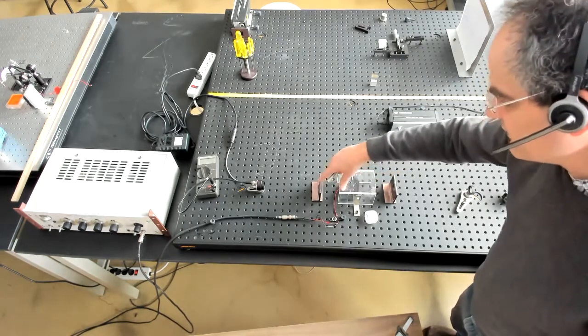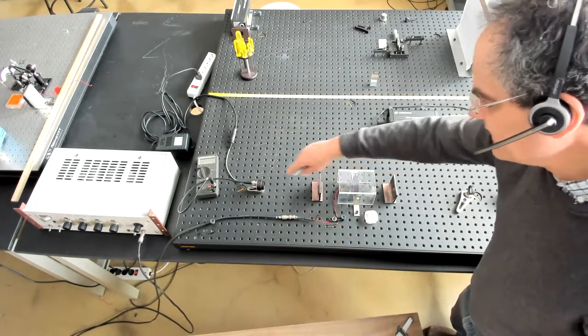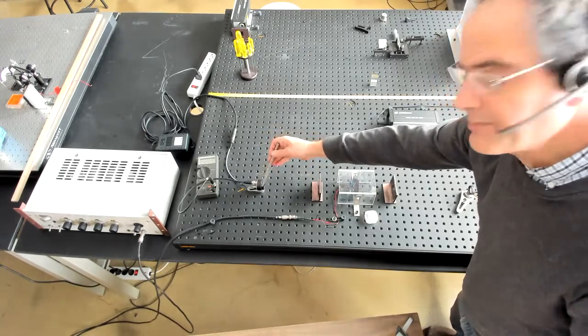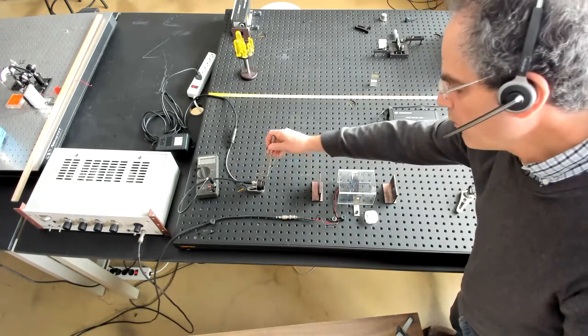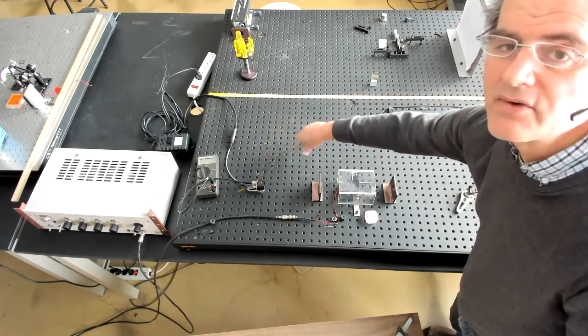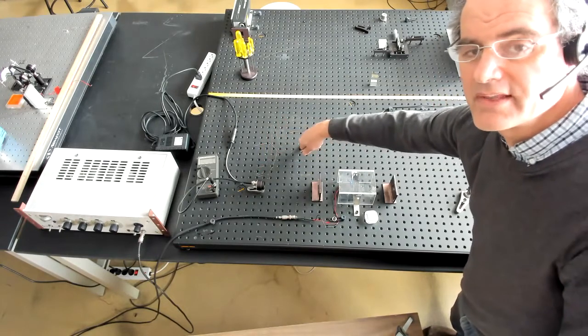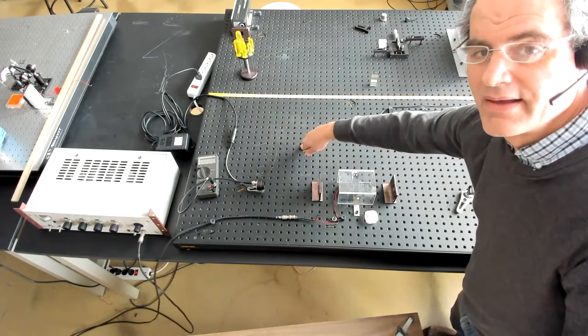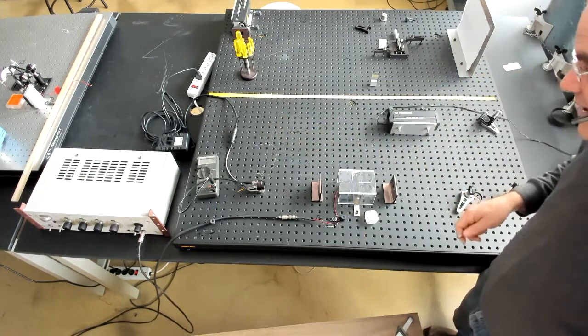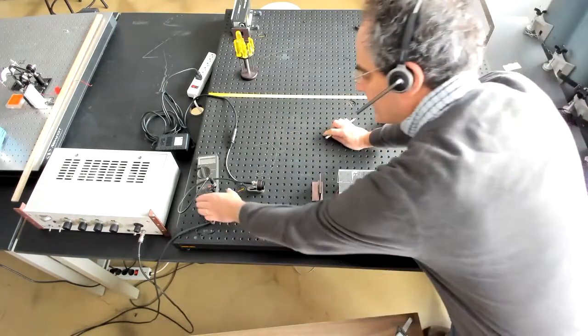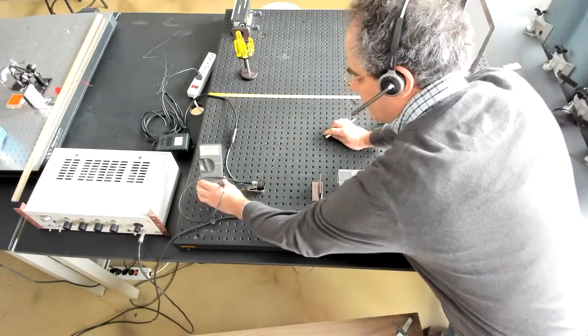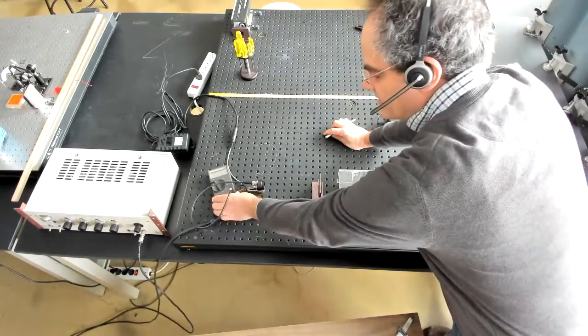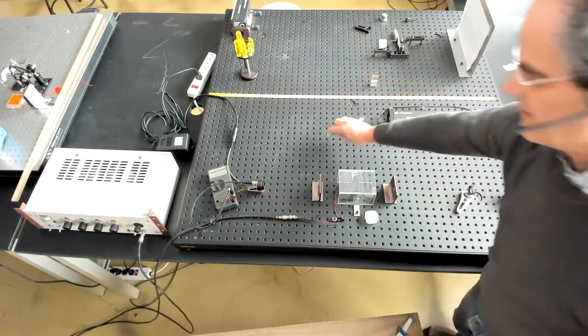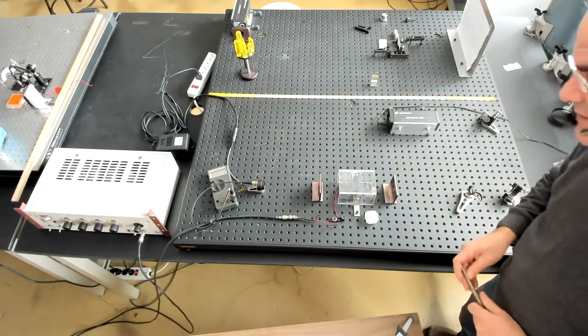Afterwards, the laser beam goes through a second polarizer, and then it either goes to an optical detector, or to a screen you place in front of the detector so you can see the beam with your eyes. That's the basic setup. Finally, we can use a digital voltmeter to measure the signal from the silicon photodiode detector.